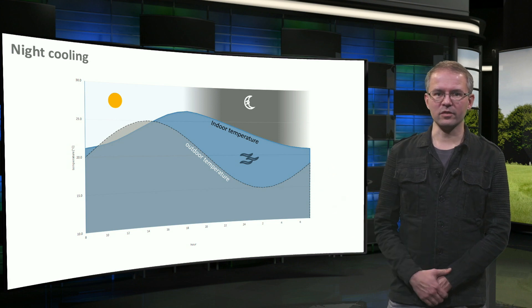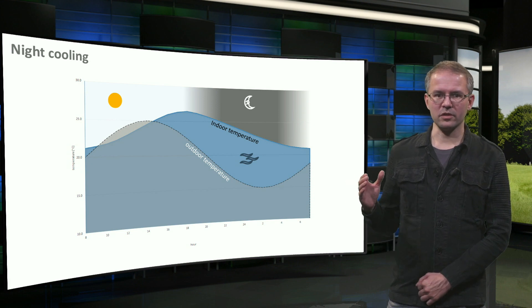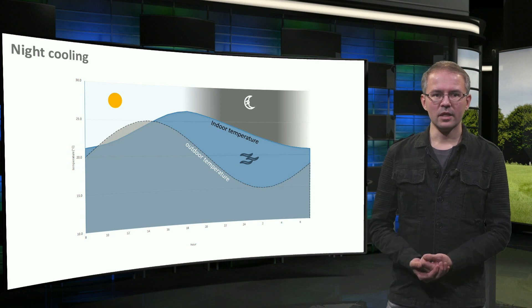This wind cowl is a modern example, used in the BedZED housing development in the UK — it automatically rotates with the wind. Night ventilation cools down the building at night so it can absorb more heat during the day. This example shows the effect of just using night ventilation: the mass of the building has cooled down so much that it takes several hours for the indoor temperature to catch up. Night ventilation does require building mass, so it will not work very well with light structures.